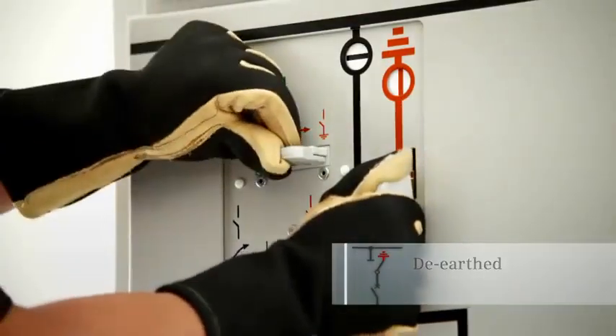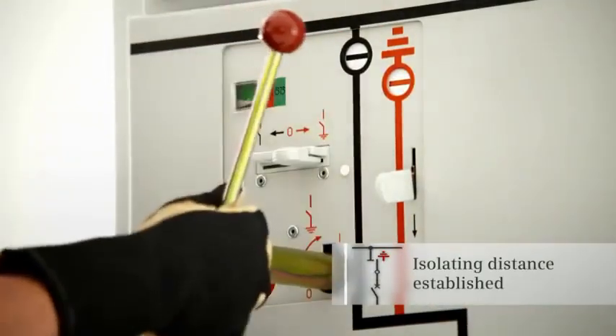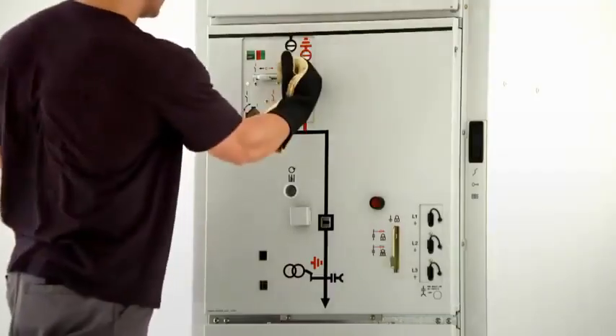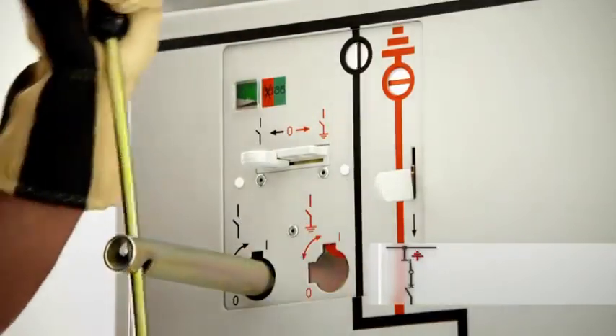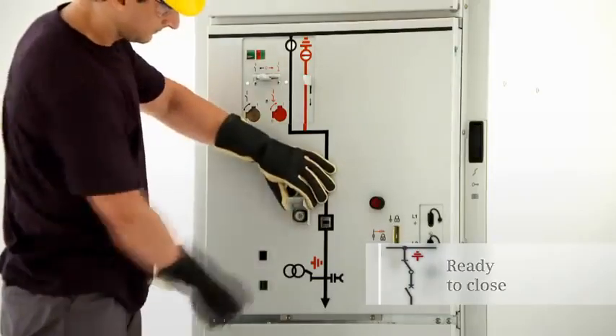The three position disconnector can then be switched from the ready to earth position to the open position and then to the closed position. The feeder is re-energized by closing the circuit breaker.